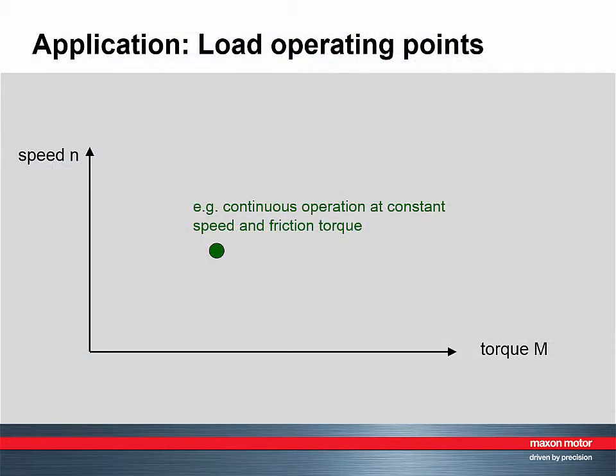The starting point for motor selection is the motion of the load in the application. The necessary operation cycles, speed profiles and friction result in speed and torque requirements the motor has to fulfill. In case of mechanical transformation — think of gears and screws — the values at the load have to be converted to the motor output shaft. In our standard diagram with motor speed as a function of torque, this can be represented as points of operation.